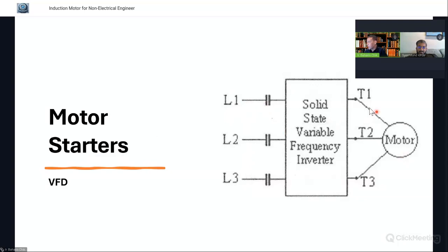Here there is no overload relay. So from the VFD it will connect to the motor directly. Inside it will measure all the parameters related to overloading, in terms of temperature and all the protection for the motors. And then from this VFD it will also connect to the DCS, to control the VFD to run at a certain set point. So all the interfaces are all here.